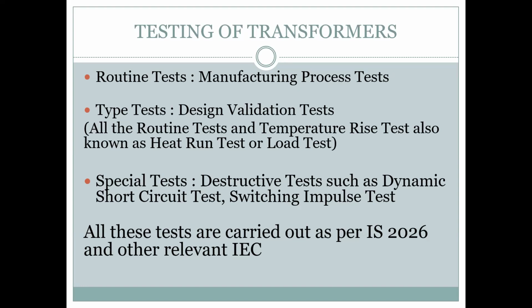Which industry is asking for this 3 seconds withstanding capacity? Basically steel industries. Where are these done? It is done at CPRI Bhopal, but for some ratings, like 500 MVA, India doesn't have the capacity. Bina is, I think, trying now. Otherwise it goes to Germany, KEMA, Holland. Those 500 MVA transformers are tested for short circuit. They do not unload from the ship; it is stationed in the ship, and the ship goes to KEMA. They are the international authority to test. Only they are permitted to carry out this short circuit test.